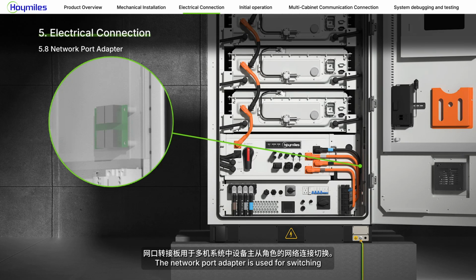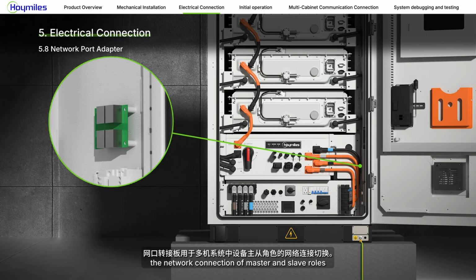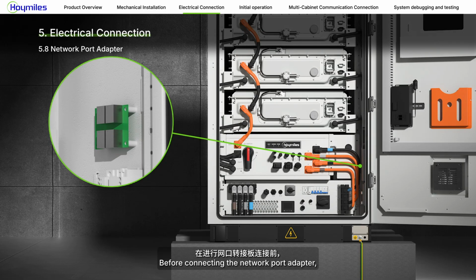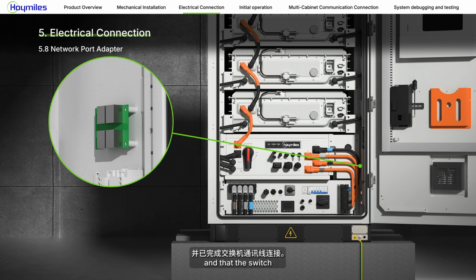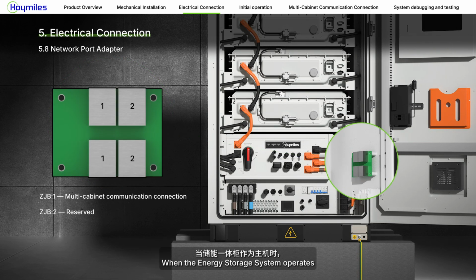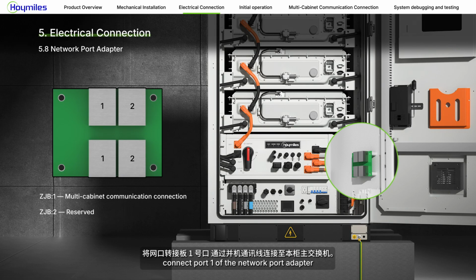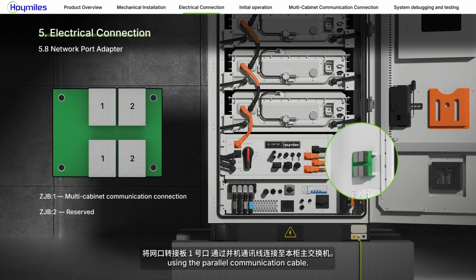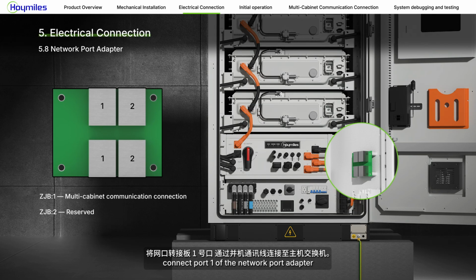The network port adapter is used for switching the network connection of master and slave roles in a multi-cabinet system. Before connecting the network port adapter, ensure that the energy storage system is powered off and that the switch communication cables have been connected. When the energy storage system operates as the master unit, connect port 1 of the network port adapter to the local master switch using the parallel communication cable. When the energy storage system operates as the slave unit, connect port 1 of the network port adapter to the master unit switch using the parallel communication cable.